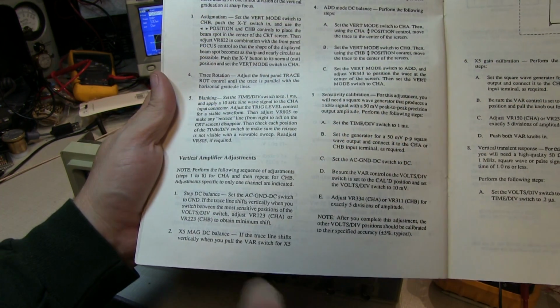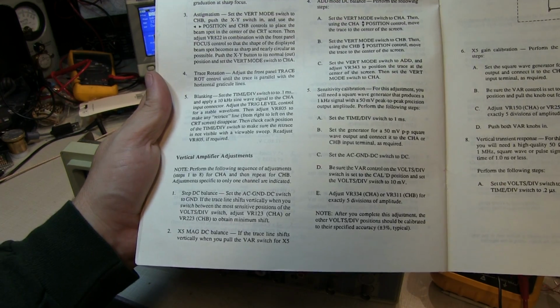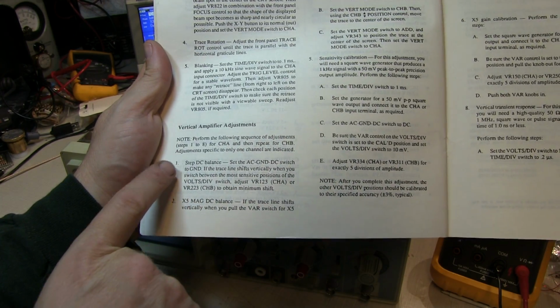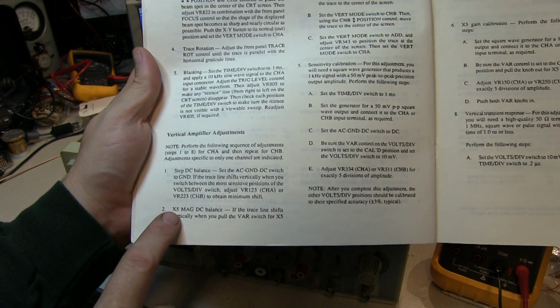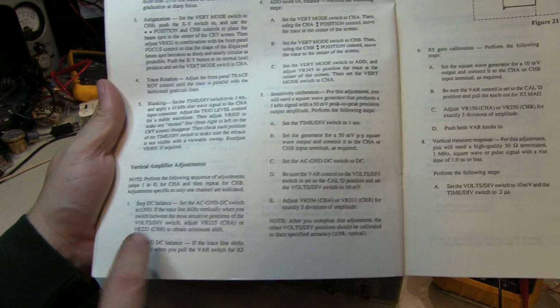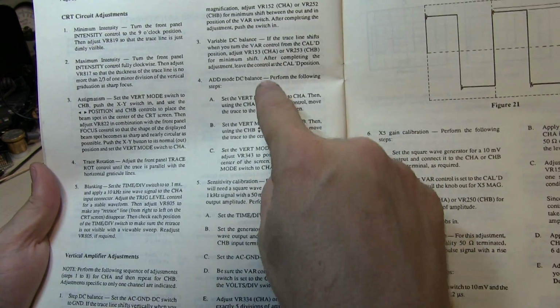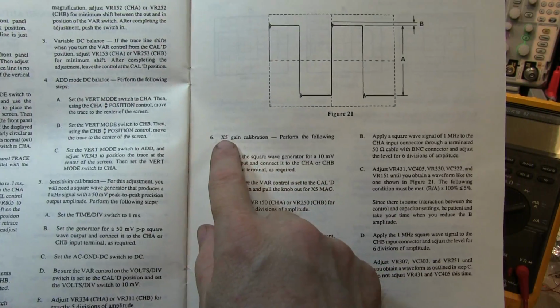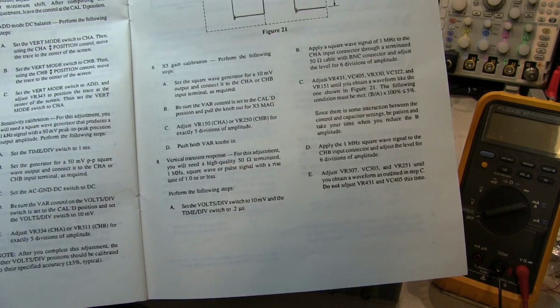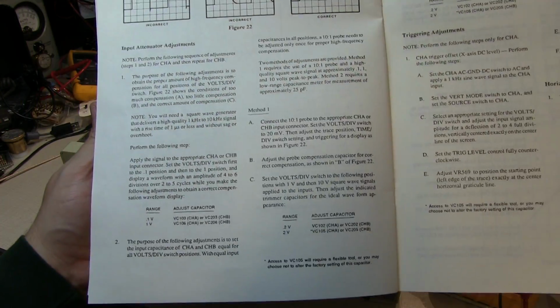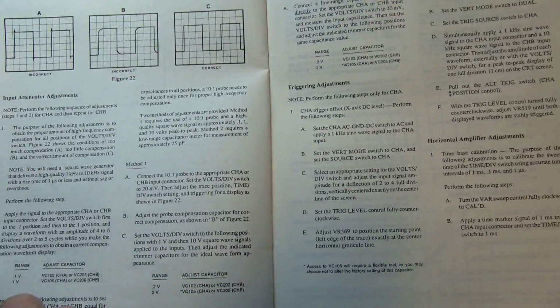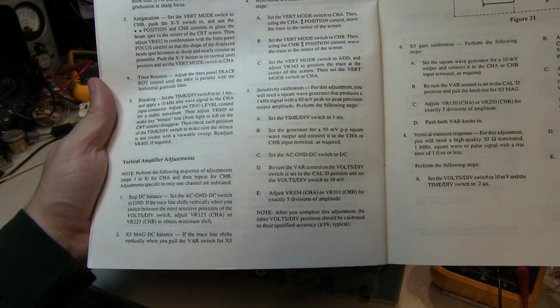Well, the next step is to go on to the vertical amplifier adjustments, and there are 8 steps. We have to check the step DC balance, the ×5 magnification DC balance, the variable DC balance, the add mode DC balance, the sensitivity calibration, the ×5 gain calibration, the vertical transient response. And then we also have to do the input attenuator adjustments, and there's a couple different methods we can use here before moving on to the trigger circuit. So we can see we'll spend a lot of time on the vertical calibration.